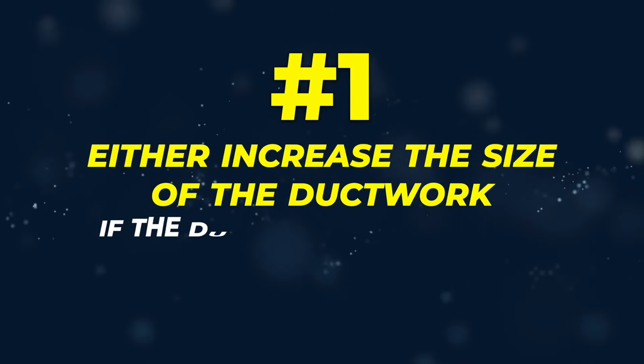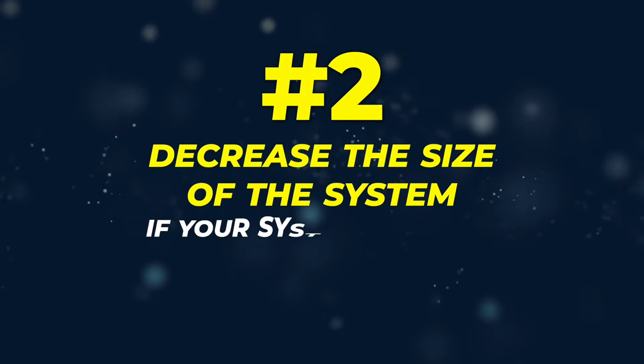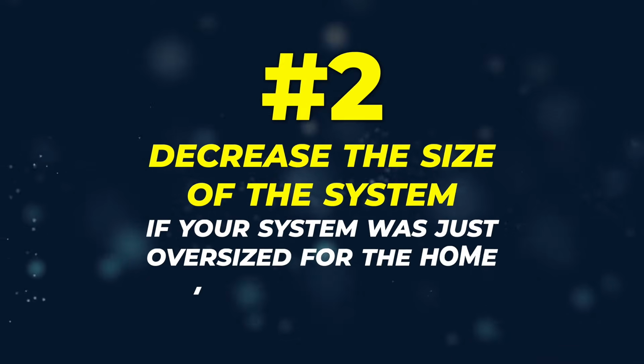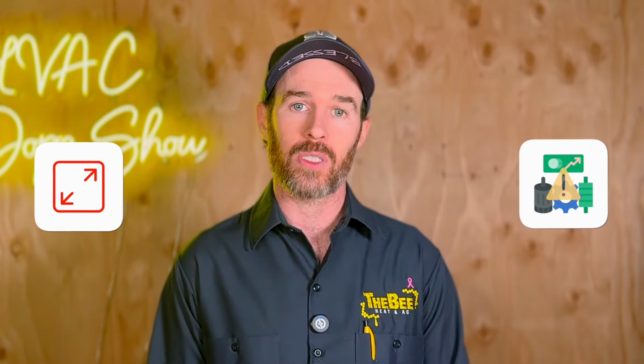And it's also going to vary depending on how the system is designed and whether or not you have enough total airflow. But the way that you can address this is basically twofold. One is either increase the size of the ductwork if the ductwork is the culprit, or two is decrease the size of the system if your system was just oversized for the home in the first place and was basically the wrong size system that was put in. Now, we do run into this personally as a company. Maybe once a year we'll have a system that was missized or we missed something on the install, and what we do is we rip it out and we put in the right size system.